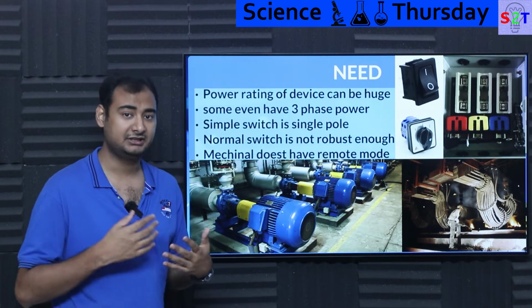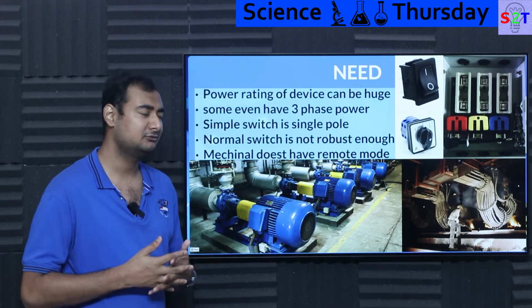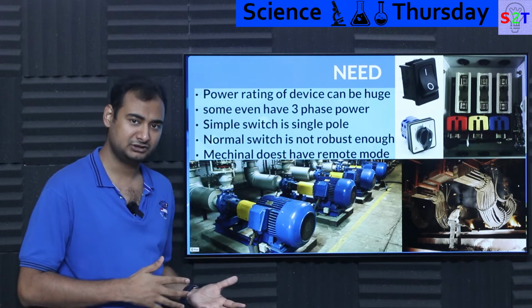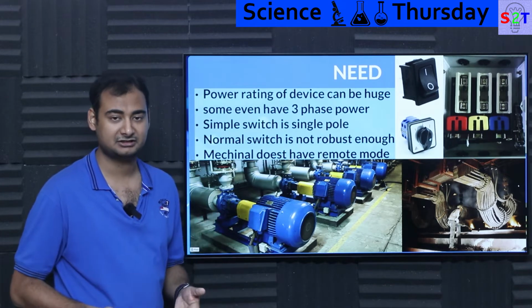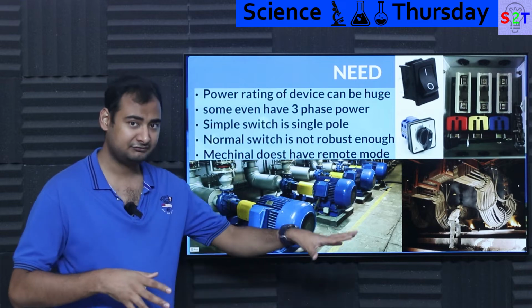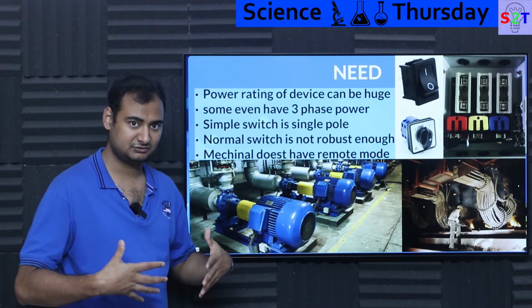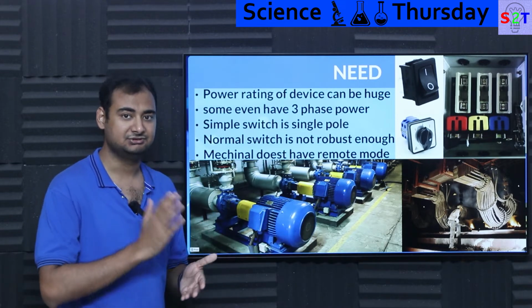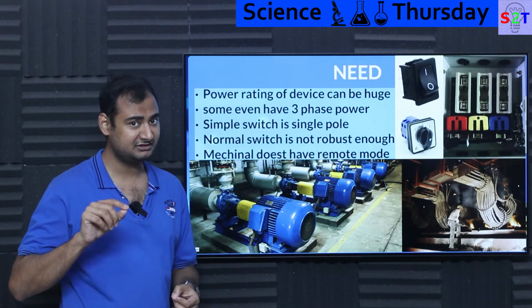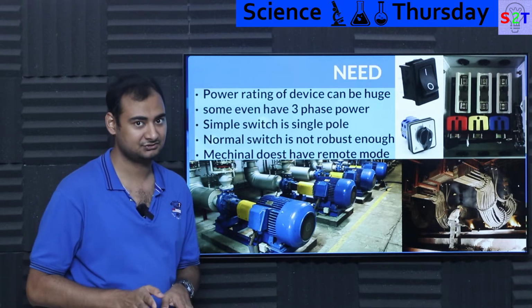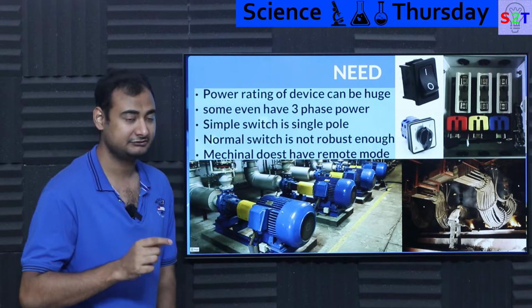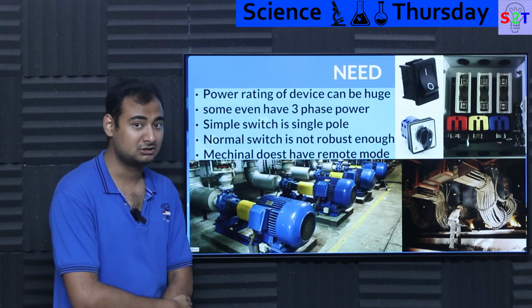Same goes with very huge inductive loads, or many appliances have smoothing capacitors and power factor correction, which, if you have a lot of them piled up together, will act like a dead short for a brief instant from the substation's point of view. But that brief instant is more than enough to destroy your switch every time you turn it on and off, and a normal switch will simply not last long enough.